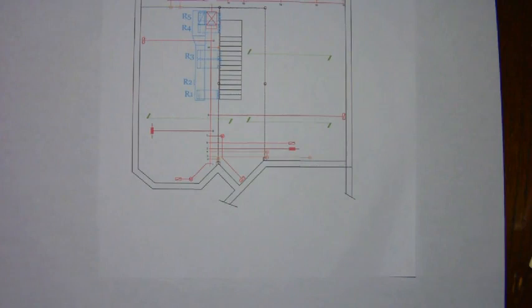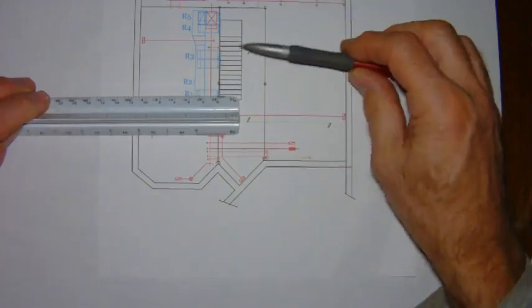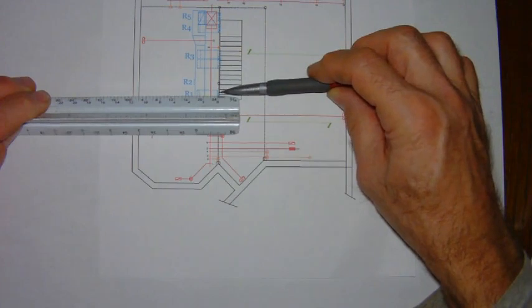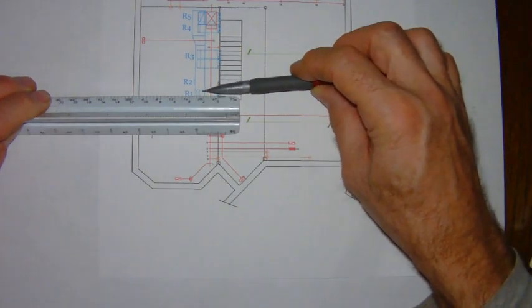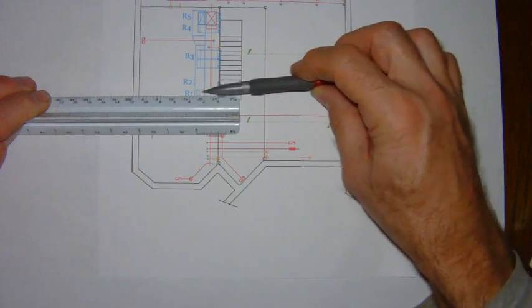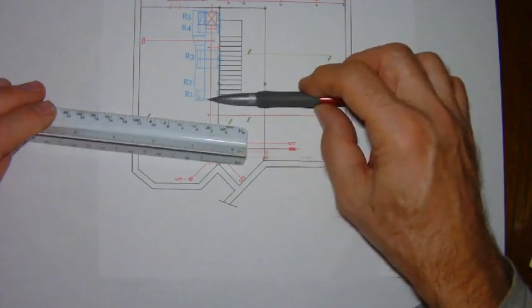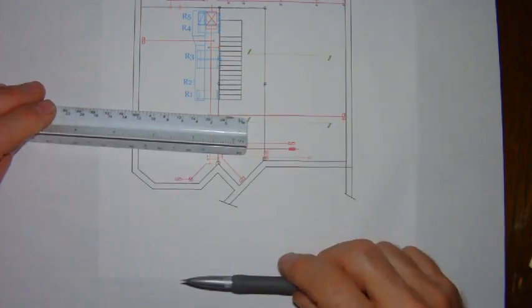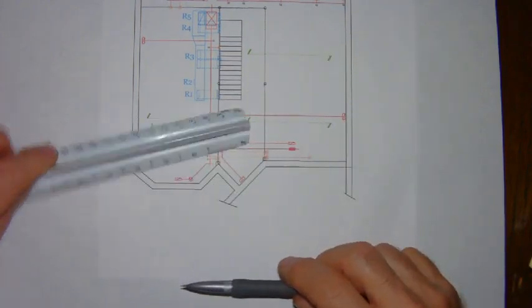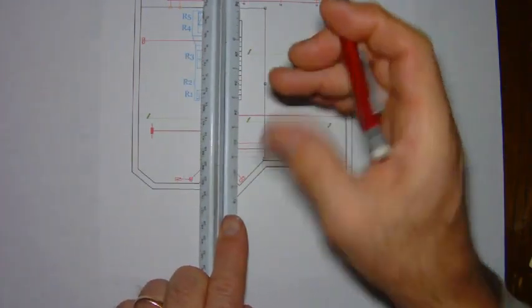Now here we can measure the horizontal distance and I recommend you simply measure from the center of the fitting over to the center of the duct. In this instance, we've got about two and a half feet, and so with duct design, you simply round that up to the next whole number.